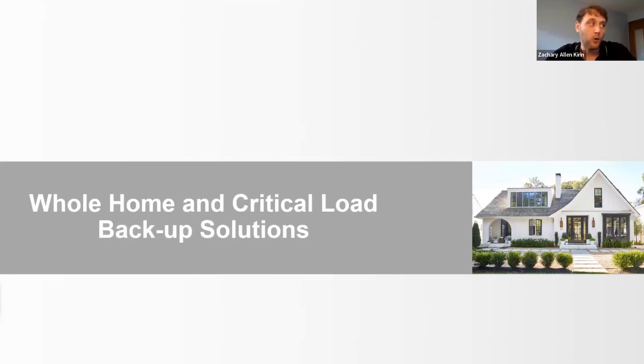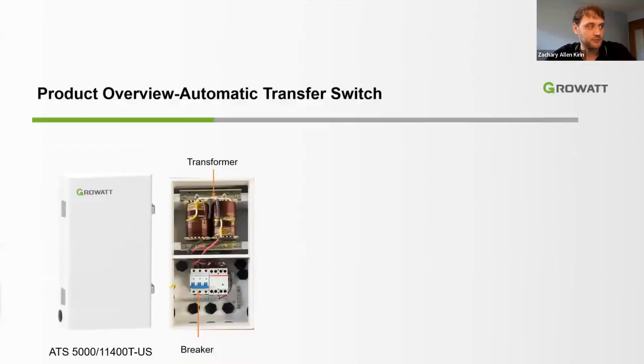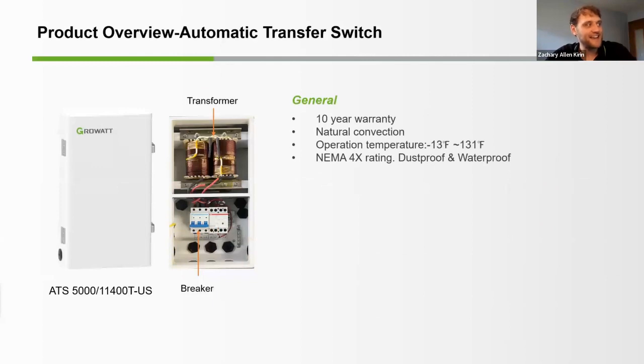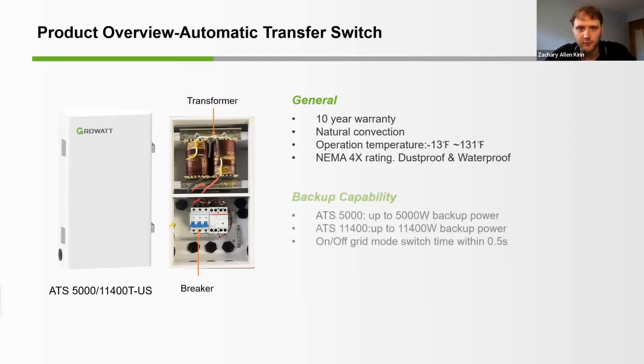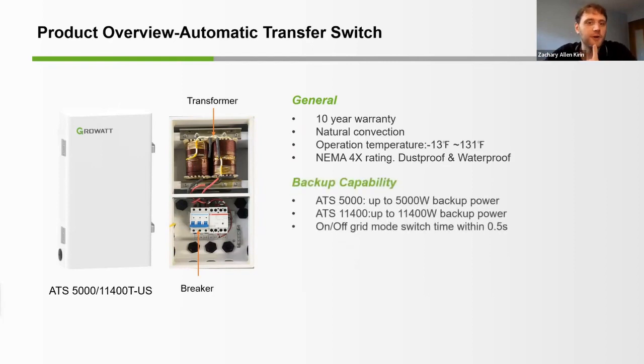Lastly, I'm going to discuss a little bit about our whole home and our critical load backup solutions. First, we have the ATS 5000 or 11400. This is a 10-year warranty device, features natural convection and an operation temperature between -13 and 131 degrees Fahrenheit. Like all of our other products, it's NEMA 4X rated, dust-proof, and waterproof. The on-off-grid mode switch time is 500 milliseconds, and depending on the device you have, it can provide up to 5,000 watts of backup power or 11,400 watts of backup power.